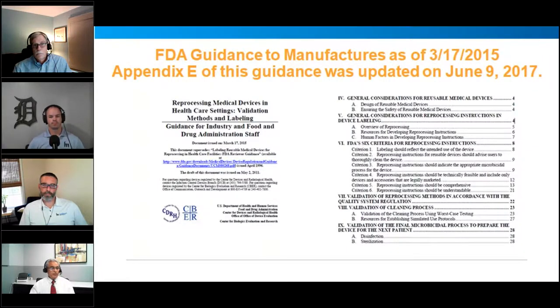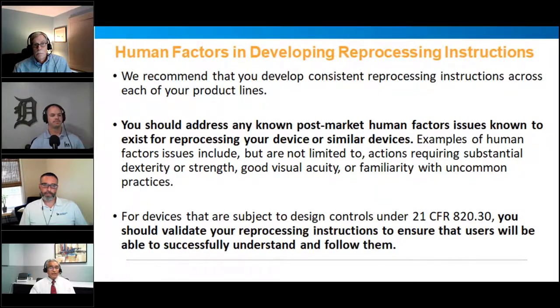If you go to the next slide, you see that in this recommendation, again, this is a recommendation, not a requirement. FDA said that we recommend that you, the manufacturer, develop consistent reprocessing instructions across each of your instruments. So if you have a tray of 20 different types of instruments, you should be able to process that entire tray the same way. You don't need to break it down into five different cleaning methods.